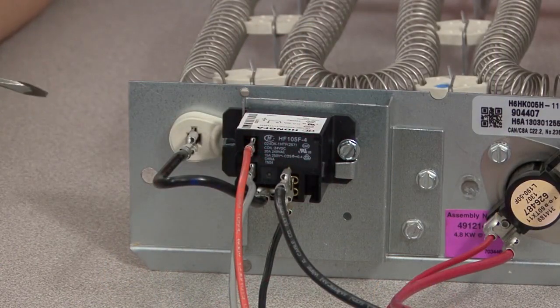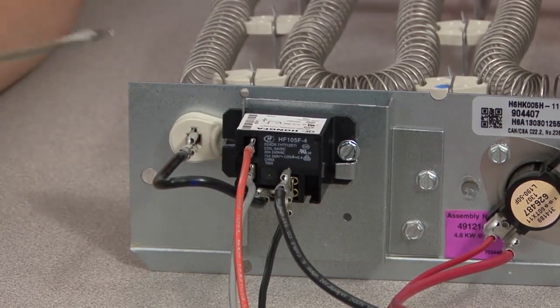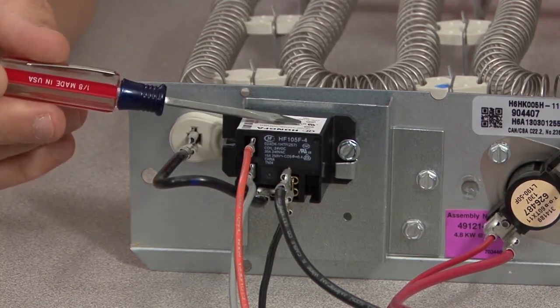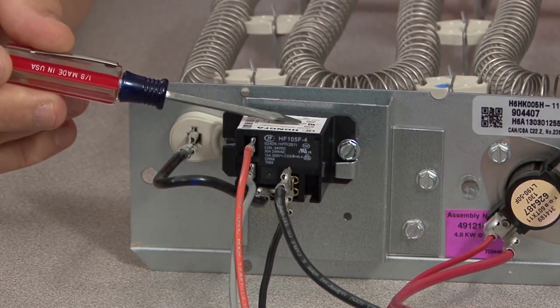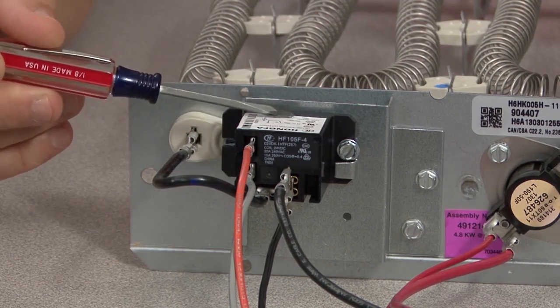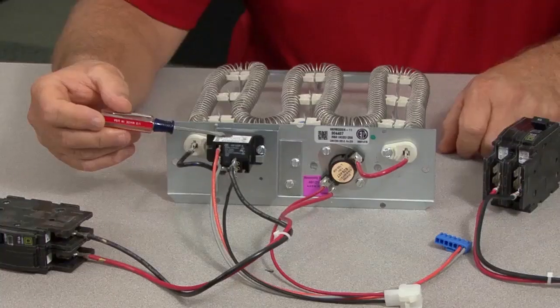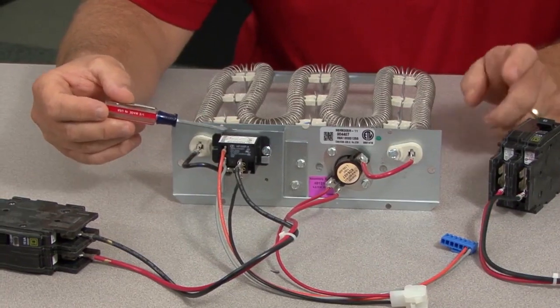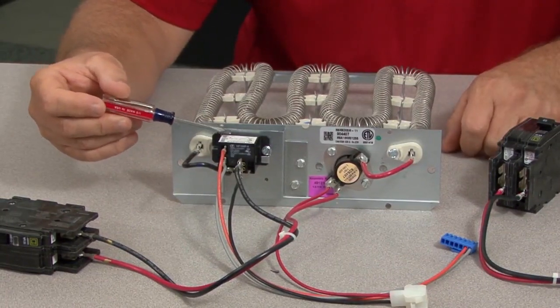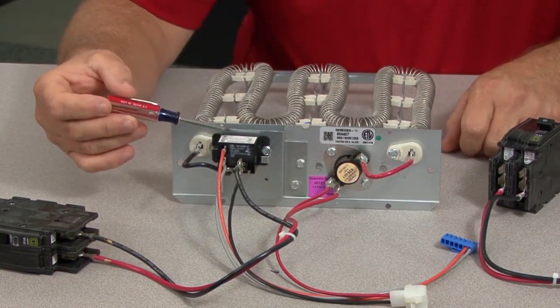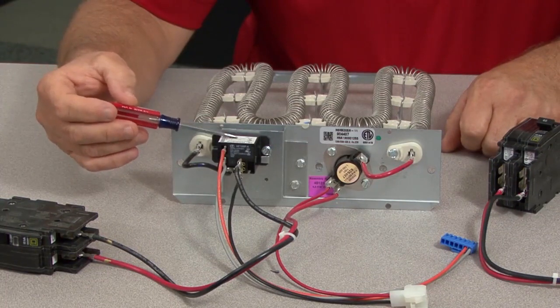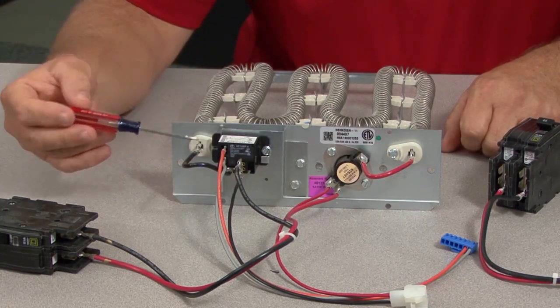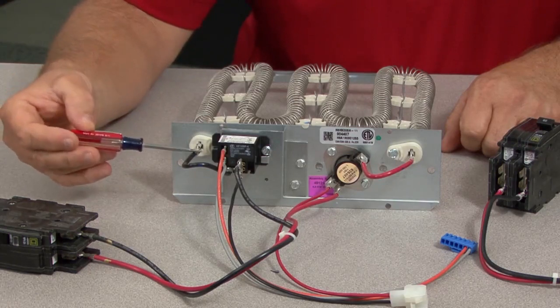The H6 heater kit was the predecessor to the H8. What you'll see on here is there's only one black relay, because this is only a 5 kW H6 heater kit. If you had a 10 kW, you'd have 2 black relays. If you had 15, you'd have 3 black relays, and so on. So in the H6, that's all we had on those heater kits, is the black relays switching the power to only one side of the element, not the other side.